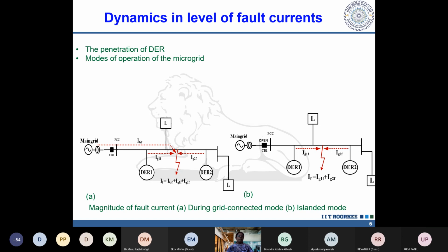When a line fault is incepted in any feeder, the sources present inside the AC microgrid will try to push current to the fault point, because the fault point is at the lowest voltage level. At the fault point the voltage dips, right? It is a basic principle in electrical engineering that current flows from a higher voltage level to a lower voltage level. So the AC main grid and the DERs present in the network will try to supply fault current to the fault point. So dynamics means the changes in the magnitude of the fault current.